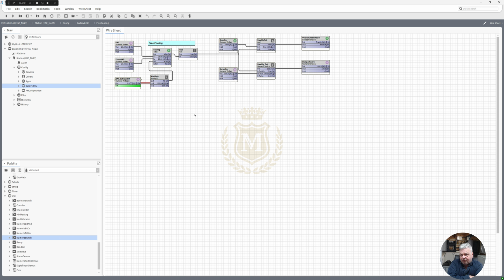Well, I think 2 degrees using normal temperature sensors would be enough for your free cooling on your air handling unit. Naturally, there's a lot more logic involved in the air handling unit, but it's as simple as that for allowing free cooling, because you can't get it from the chiller, because that's not free. That's costing you to make that cold water. You can only get it from outside air. That's the only way to do free cooling.